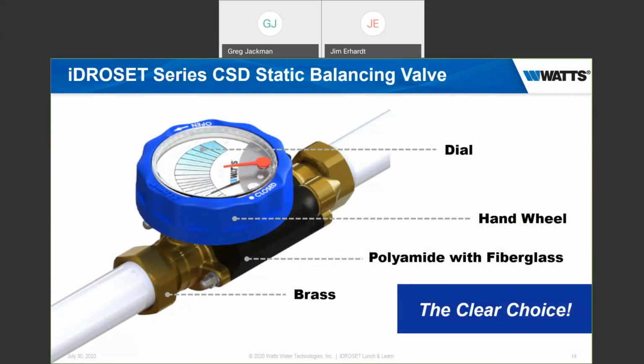The red needle on the top is simply a needle you manually set to the design flow rate. So if the call out is for 2 GPM, you just manually set the red needle to 2 GPM, and then you'll adjust the iDROSET valve to achieve the 2 GPM, so the black needle lines up with the red needle. The hand wheel on the outside is actually what you use to adjust the flow rate.